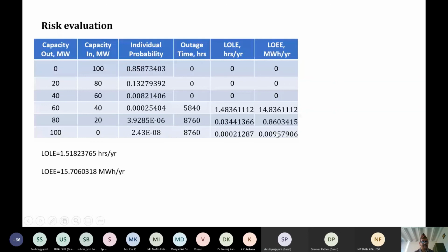Similarly, this and these are also obtained in the similar manner. Although the energy value here and here will be higher, but the probability value are lower. Therefore, loss of energy expectation are lower here. And you can see loss of load expectation is 1.518 hours per year. This is when we used this load model. This is hourly load model. Okay, this is LOLE when we used hourly load model. So okay, so we used hourly load model. Therefore, this LOLE value has been in hours per year.